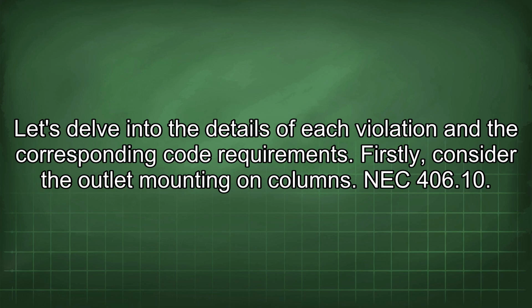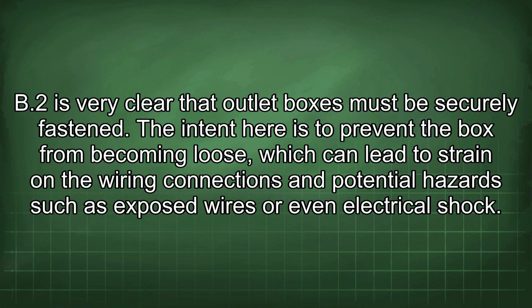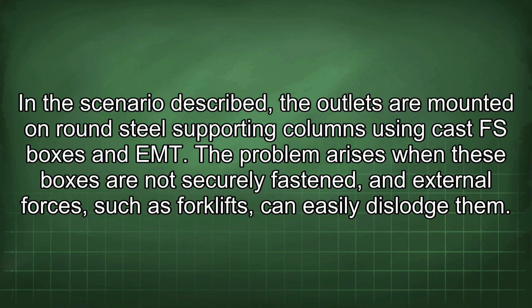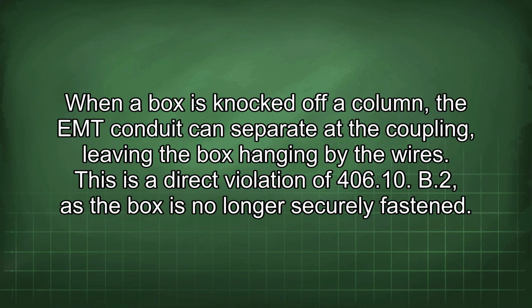Firstly, consider the outlet mounting on columns. NEC 406.10.B2 is very clear that outlet boxes must be securely fastened. The intent here is to prevent the box from becoming loose, which can lead to strain on the wiring connections and potential hazards such as exposed wires or even electrical shock. In the scenario described, the outlets are mounted on round steel supporting columns using cast FS boxes and EMT. The problem arises when these boxes are not securely fastened, and external forces, such as forklifts, can easily dislodge them. When a box is knocked off a column, the EMT conduit can separate at the coupling, leaving the box hanging by the wires. This is a direct violation of 406.10.B2, as the box is no longer securely fastened.